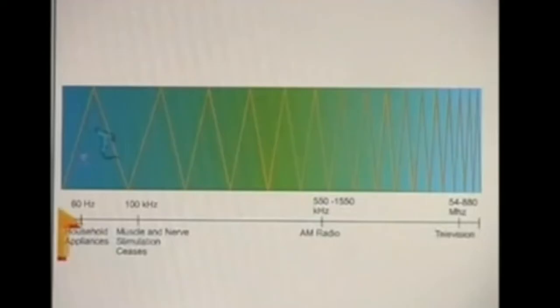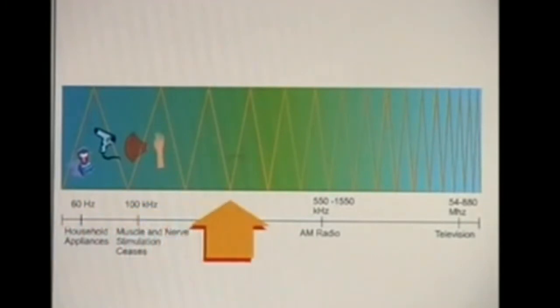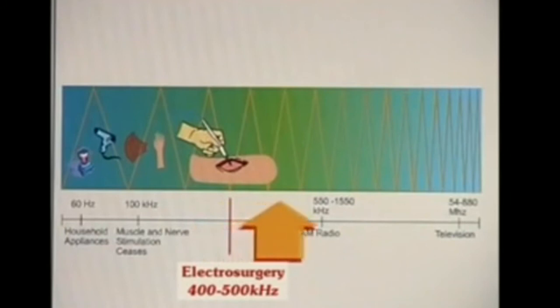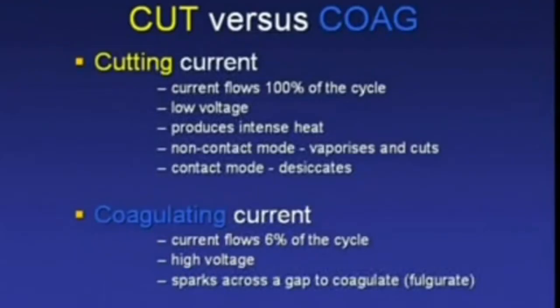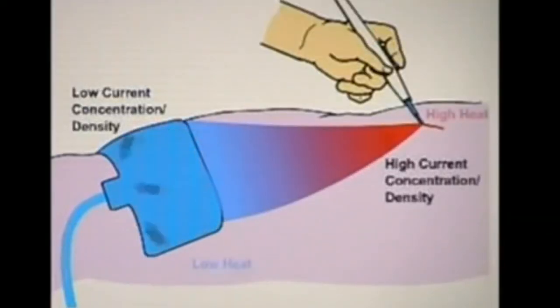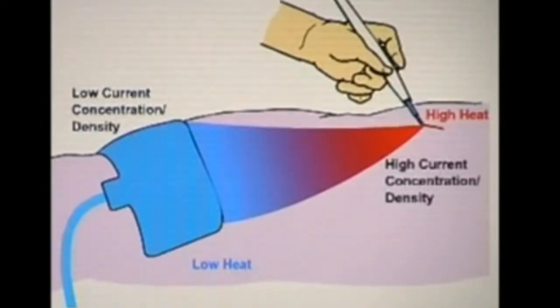To sum up some of the key facts. Electrosurgery can be used without electrocuting the patient because it is high frequency, between 400 and 500 kHz. Cutting current flows 100% of the time, has a lower voltage than coagulating current, and produces intense heat which vaporizes cells. Coagulating current flows as little as 6% of the duty cycle, has a higher voltage than cutting, and provides effective tissue hemostasis. The pad or patient return electrode does not earth the patient. It completes the circuit back to the electrosurgical generator and is not an earthing device.